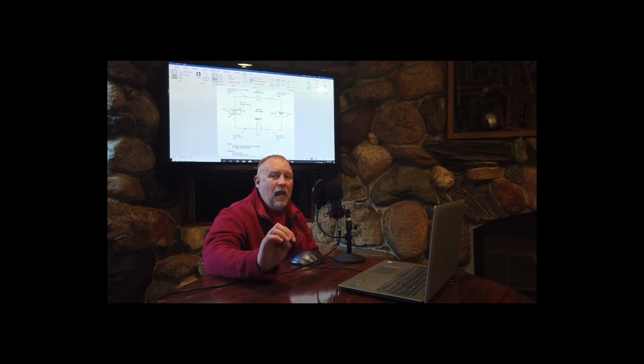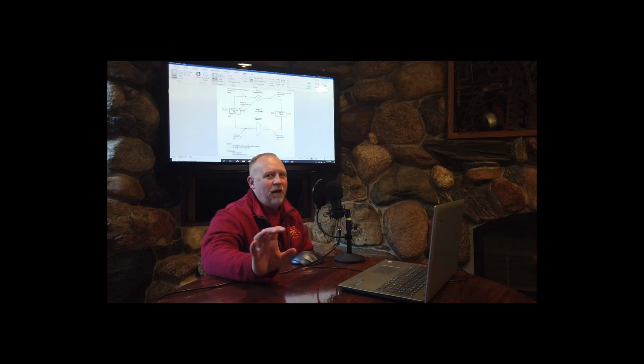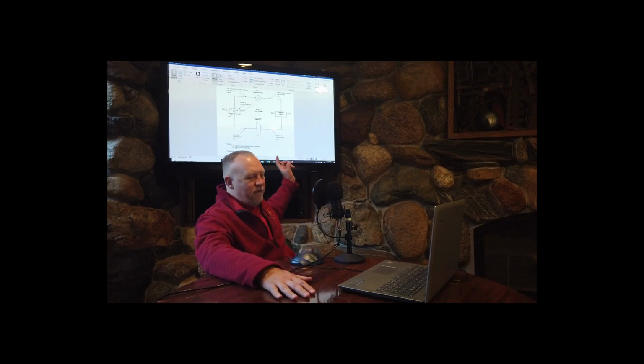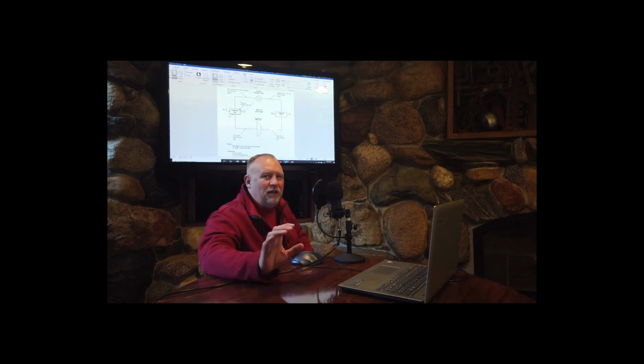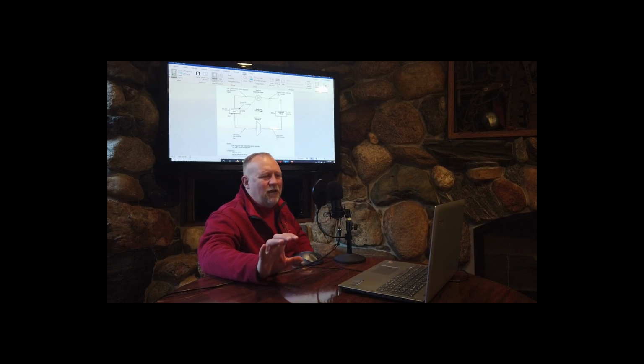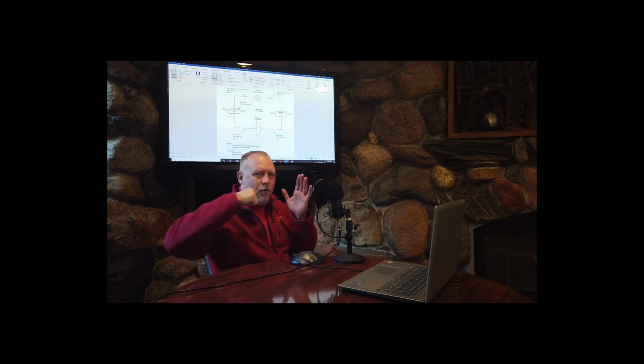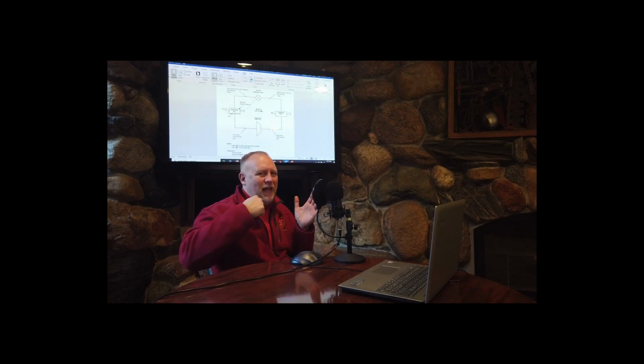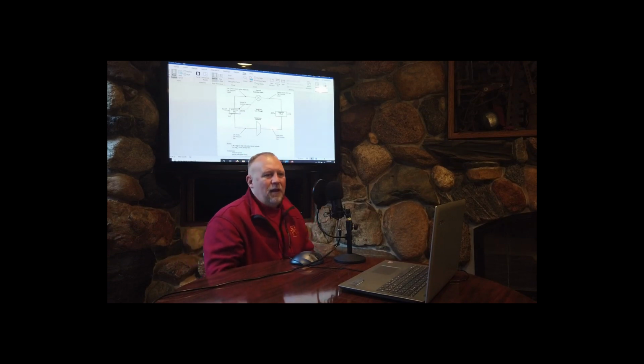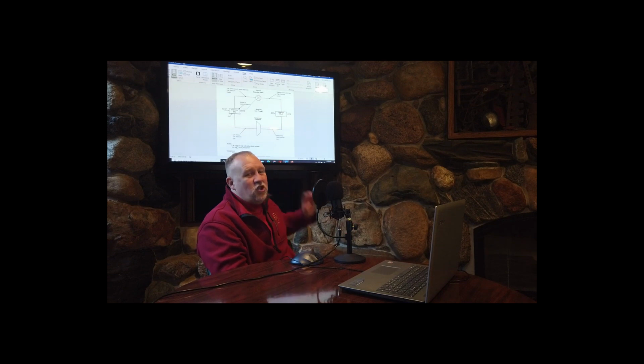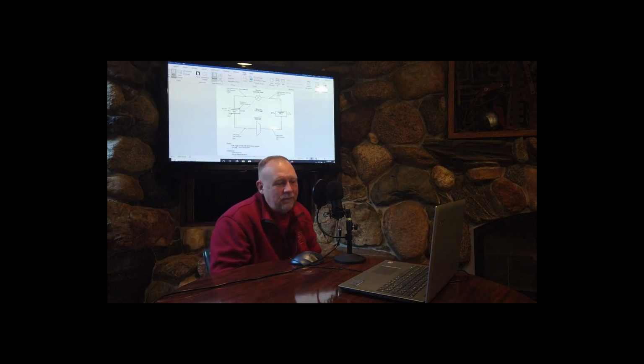Note, if any liquid refrigerant was to leave the evaporator, that would be a very bad thing, because, hopefully, once again, physics kind of subject, if a liquid gets to the compressor, the liquid cannot be compressed, although the compressor will try, which means it could easily damage the compressor, cause a bunch of damage. As the compressor tries to compress a liquid, it's basically just like hitting it with a sledgehammer. Internally, it has controls that should shut it down if that happens, but it can still damage it.